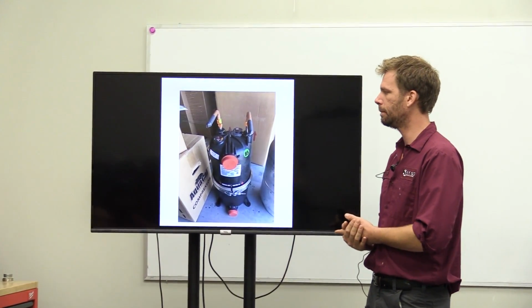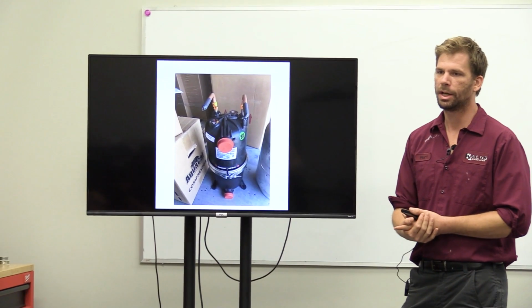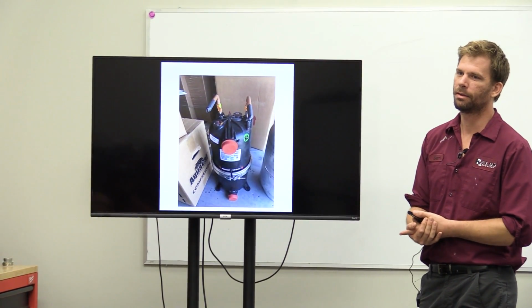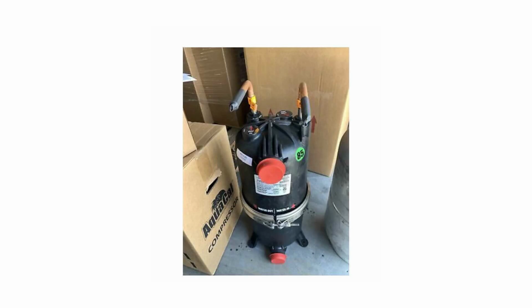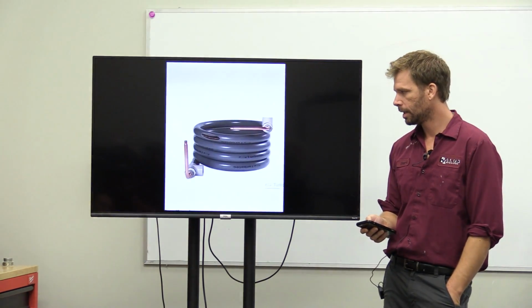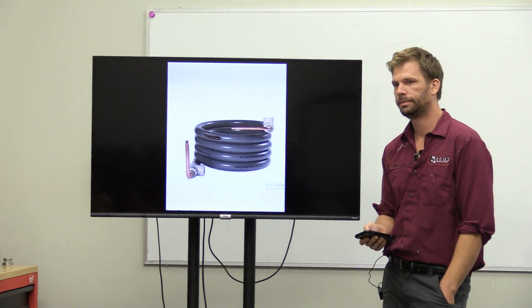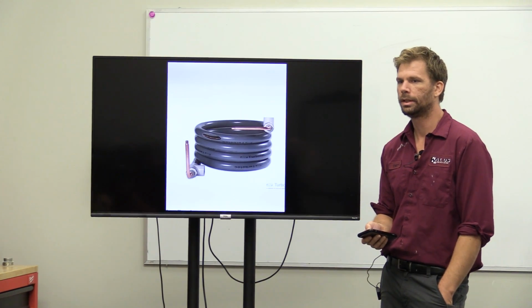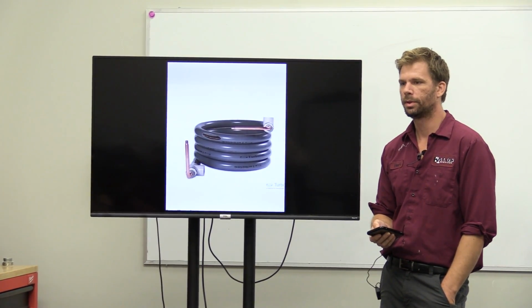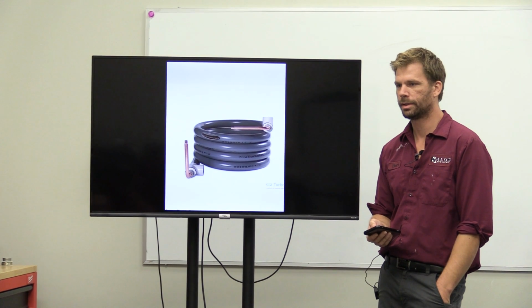But if you come up to a system and you go to hook up your gauges and water starts spilling out of the lines, the only way water could have gotten into the copper is inside of this guy. You have your copper lines going in, so you immediately know you have a heat exchanger that has blown out, a copper line has blown out inside the heat exchanger and it's got to be replaced. So, unless you have a pretty new heater that is likely under warranty, heat exchanger is a pretty extensive project. You got more work than a compressor.